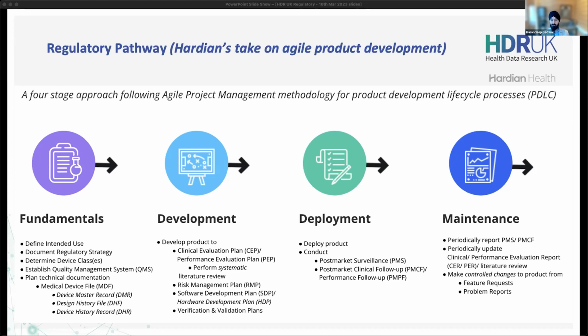Now, this is an important one. A lot of people don't know the difference between verification and validation, so I'm going to explain it to you. As people can see, I'm wearing a jacket. Verification is, does this jacket have 2 holes for arms? Does it have buttons on there, etc.? Validation is, does this jacket actually fit me? Is it actually fit for purpose? And is it doing what I need it to do? So that's the difference between verification and validation.